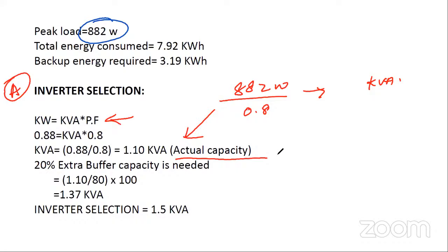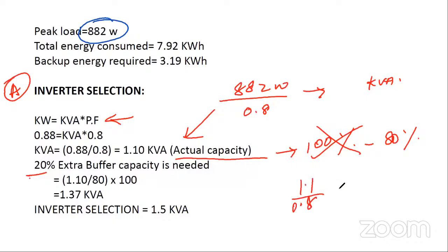But practically, you should not load 100%. You should load only 80% of the inverter, considering future expansion of 5% as well as the thermal stability of the device under load. So with a 20% extra buffer, you load only 80%, which means if 1.1 is 80% of its capacity, then what is the 100%? If you divide by 80 and multiply by 100, it gives approximately 1.37 kVA.